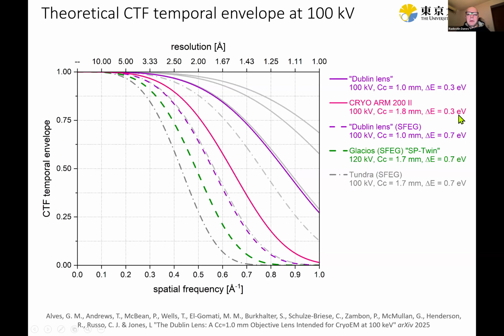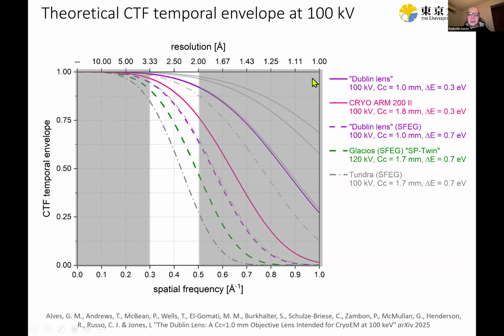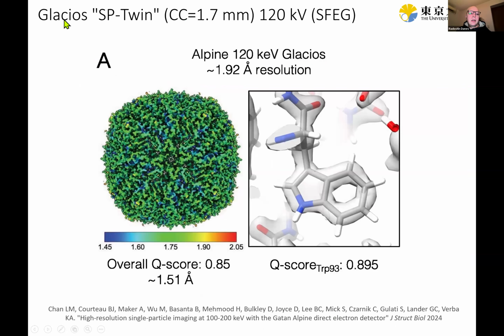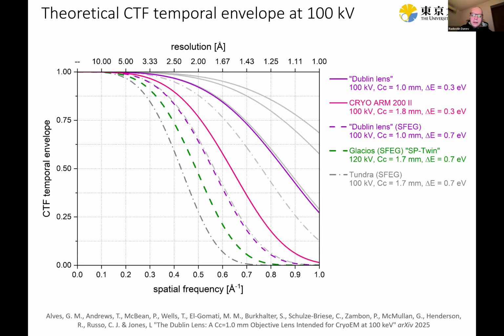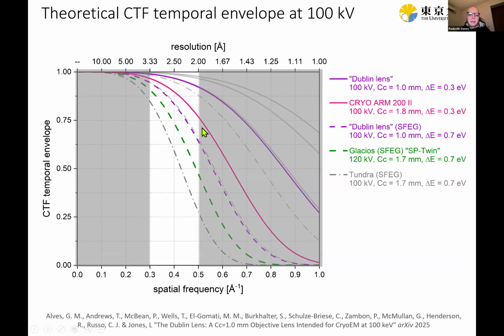In any case, if you combine the Dublin lens with the CFEG, the cold FEG, it will provide almost uncompromised optical performance in the 3 to 2 angstrom range. Now the Cryo-ARM 200 with the narrow gap pole piece already starts to hit a bit below 2.5 angstrom, and then the other machines like the Glacios with the narrow gap. I forgot to mention the Gabe Lander dataset here was collected on a Glacios with a narrow gap objective lens. So it's a 1.7 millimeter with the Schottky FEG though, so it's not a cold FEG like the Cryo-ARM. And then we have the Dublin lens with the Schottky FEG.